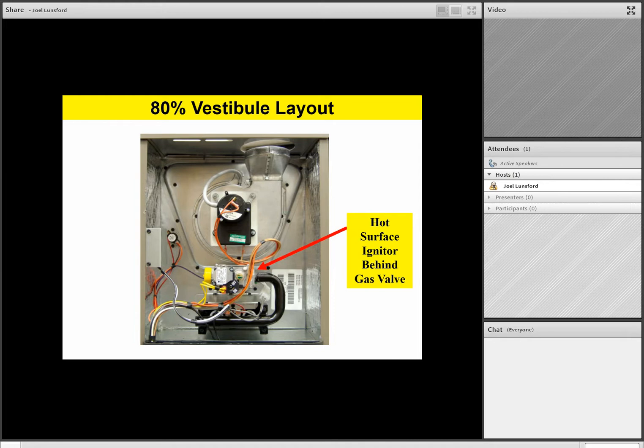The hot surface igniter sits behind the gas valve. And then we see in our example here, it looks like we have a single stage gas valve. And this gas valve, remember, it does have an on-off switch on there, so be sure that the switch is in the on position. Can't tell you the number of service calls I've had where the technician is called in with a problem with the gas valve and he had forgot to turn it on. So be sure that the switch is in the ON position, please.